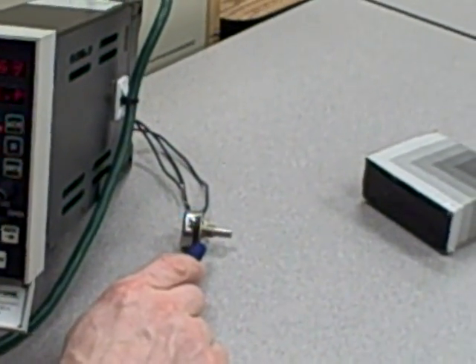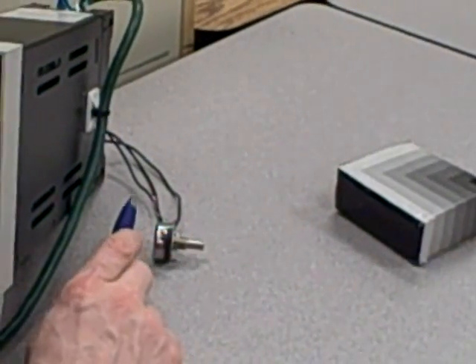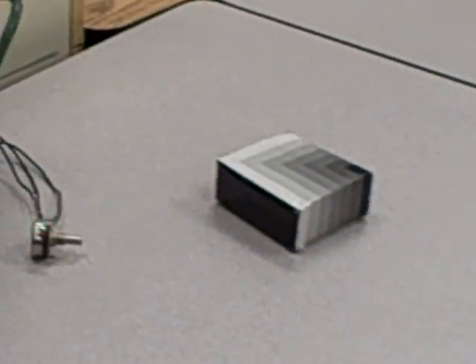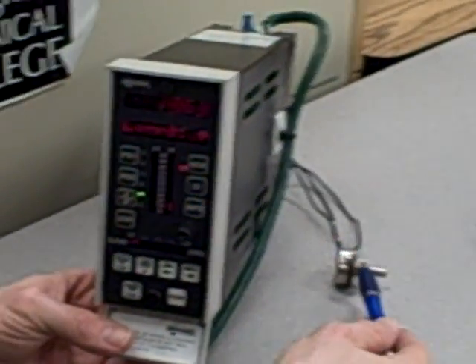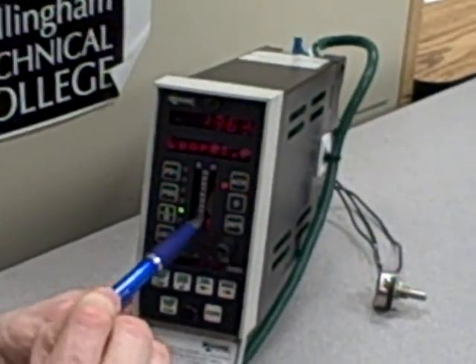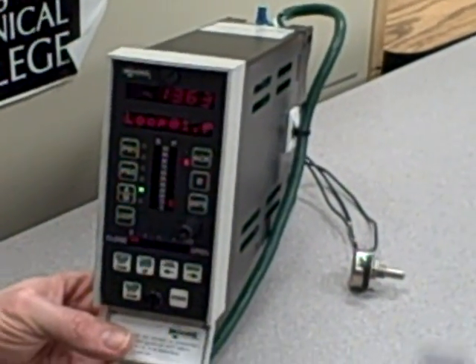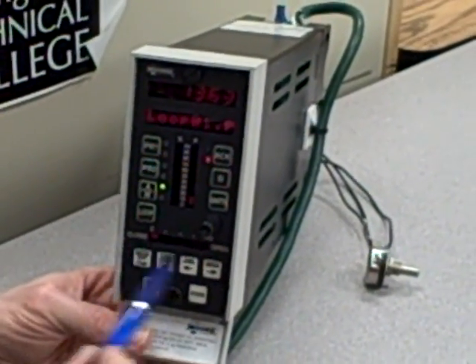We have an analog input right here. It's a potentiometer connected to analog input number one. We have fed that analog input signal into the input of the lead-lag block, so we can now set the lead and lag time constants, and the output of this lead-lag block now goes to the output scale on the controller. So my potentiometer, my analog input, reads on the P bar graph. My output of the lead-lag block reads on the valve bar graph.